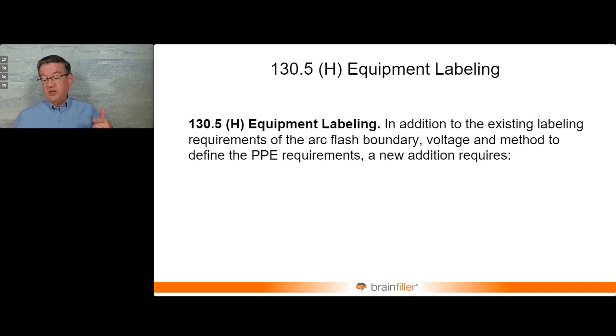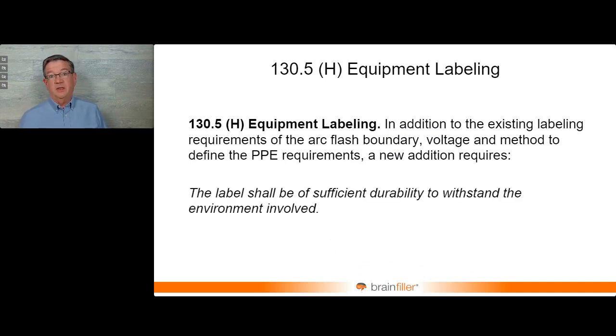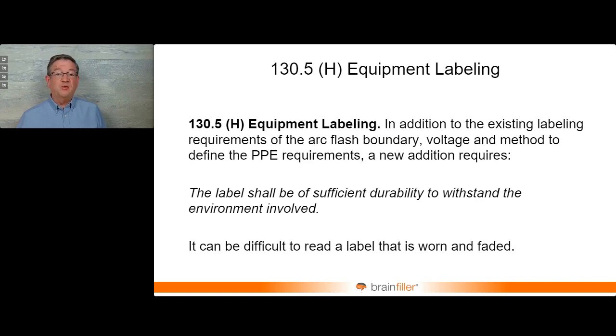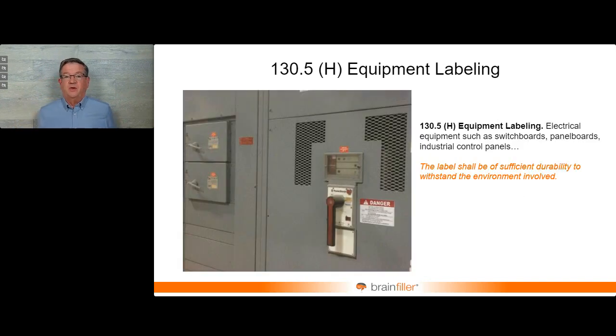So the new addition for equipment labeling is that the label has to be of sufficient durability to withstand the environment involved. So really important, because it can be difficult to read if you have a label that's faded out over time. You're going to see a label fade right here before your very eyes. About a 7-year time lapse on this. And that's bad, because now you're going to have to read it to determine the information to perform an arc flash risk assessment. That's going to be difficult.